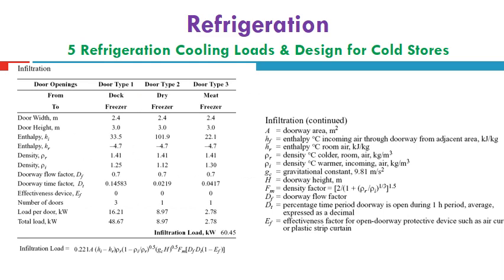Here he estimated the infiltration load by using the equation of Gosney, which is listed below this table, after listing all the door types: type 1, type 2, type 3. He has three types: one between the dock and the freezer, one for the dry freezer, and one for the meat freezer, which are the two adjacent spaces listed in this example. So he can finally get the total loads of each doorway.